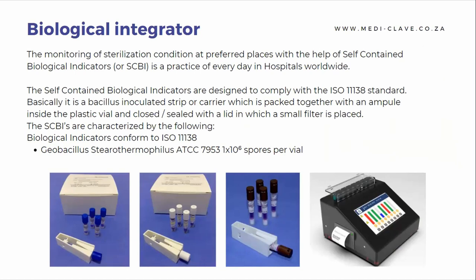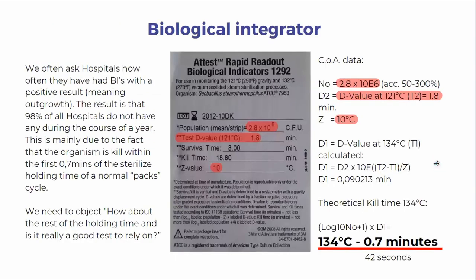We often ask hospitals how many times they have a BI with a positive result, meaning outgrowth. The result is that 98% of hospitals do not have any during the course of a year. So the main reason for that is that in a normal pack cycle, the organism is killed within the first 0.7 minutes of the sterilization holding time. We must object, how about the rest of the holding time? And is it really a good test to rely on?